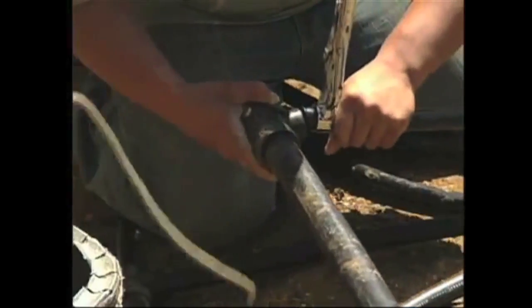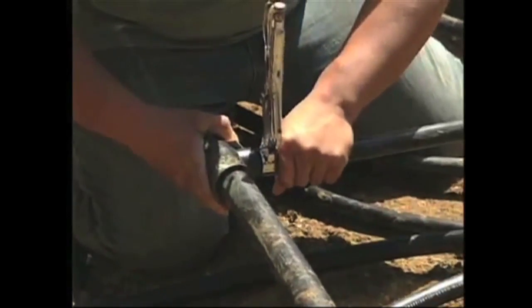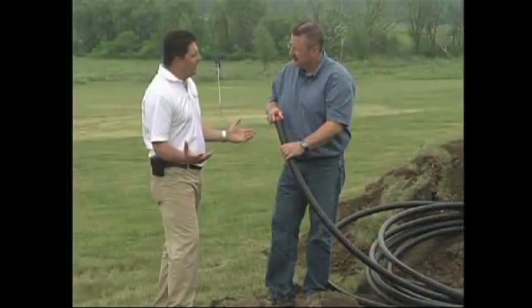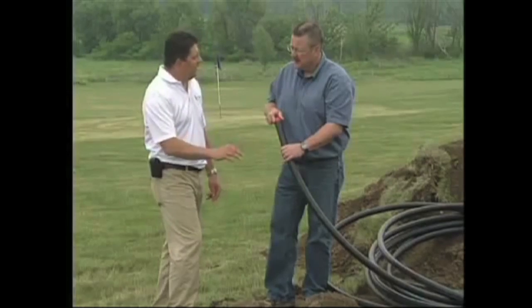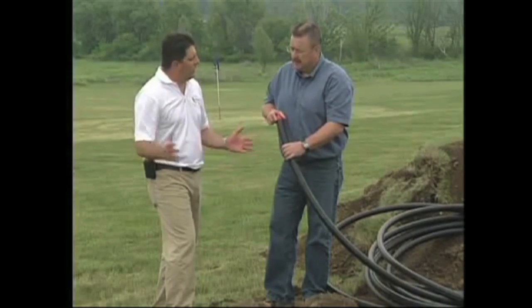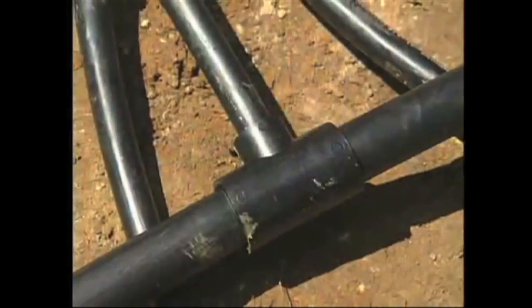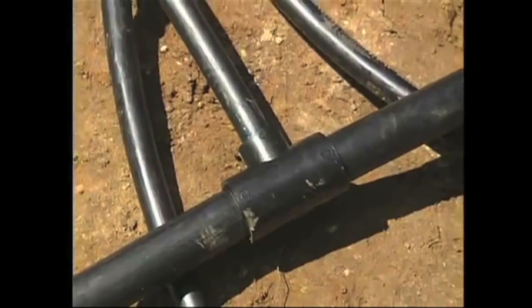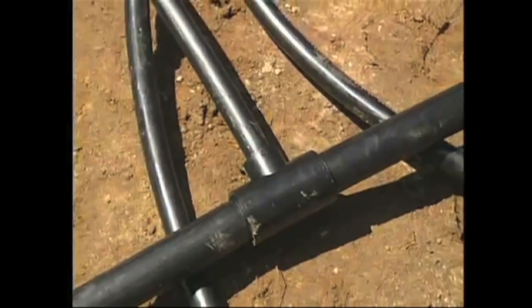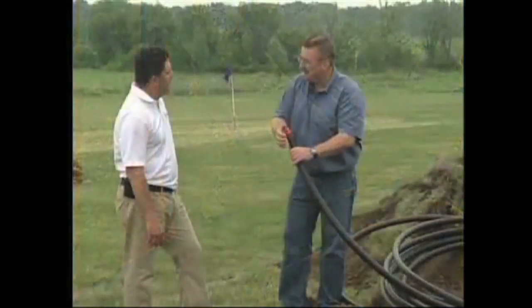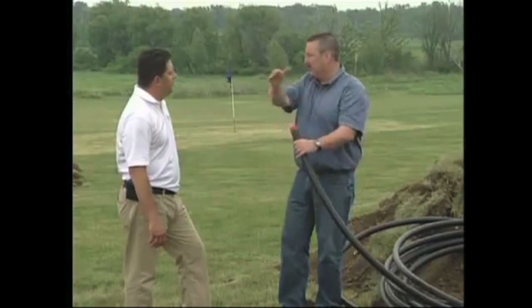We fusion weld those pipes to this pipe, so it all becomes one piece, and there are no mechanical fittings that could have a potential leak down the road. So really an excellent, reliable system. When the system is done and there's a manifold in place, it looks like there are mechanical joints, but since you melted the piping and fused it together, it all became one continuous loop. That's exactly right.